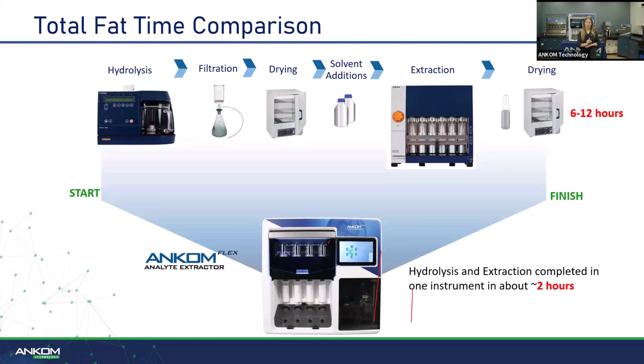It can run 4 assays per run in about 2 hours. Sample size is typically 1 gram for total fat. Again, everything is done in an inert nitrogen environment. It reduces the technician time to 10 to 15 minutes per run. So really the user will simply assemble their vessels, weigh their sample, place it in the instrument and press start. The instrument does not need to go in a hood. We have exhaust lines that you can run to your hood or exhaust system, so it frees up that valuable space. And you have the ability to adjust method parameters, which I will share a little bit more on as we go.